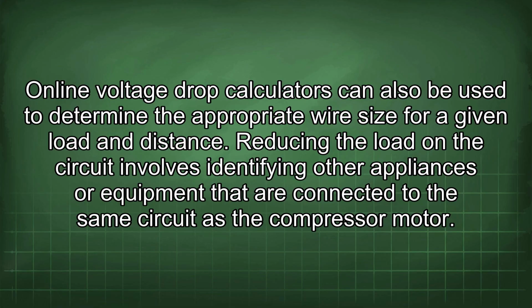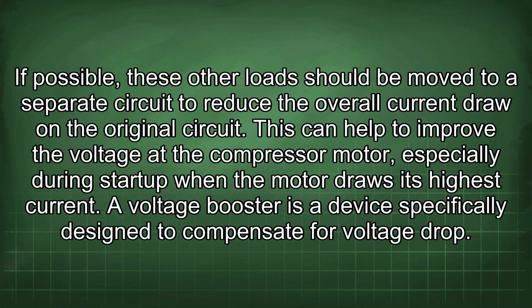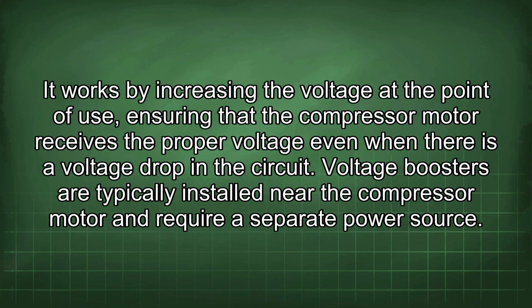Reducing the load on the circuit involves identifying other appliances or equipment that are connected to the same circuit as the compressor motor. If possible, these other loads should be moved to a separate circuit to reduce the overall current draw on the original circuit. This can help to improve the voltage at the compressor motor, especially during startup when the motor draws its highest current. A voltage booster is a device specifically designed to compensate for voltage drop. It works by increasing the voltage at the point of use, ensuring that the compressor motor receives the proper voltage even when there is a voltage drop in the circuit.